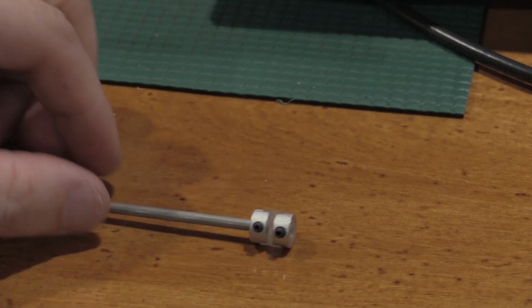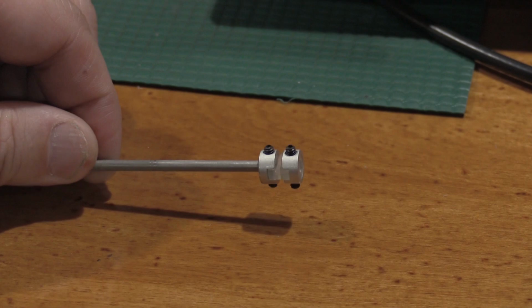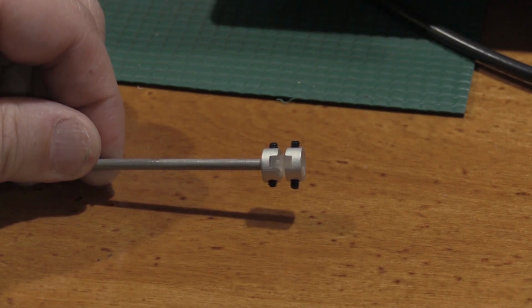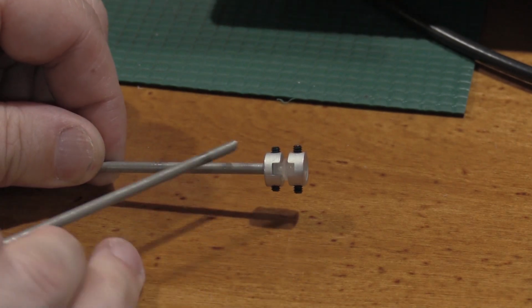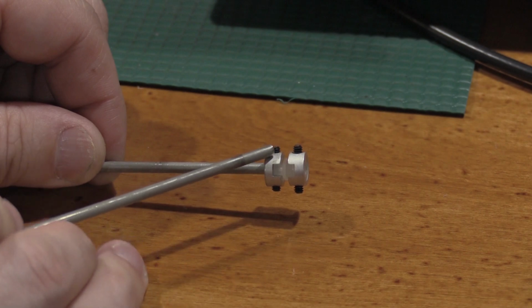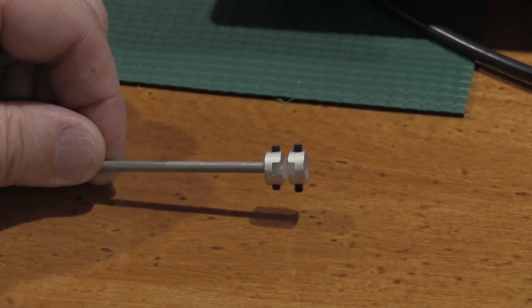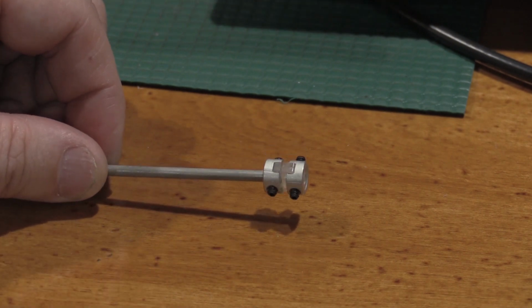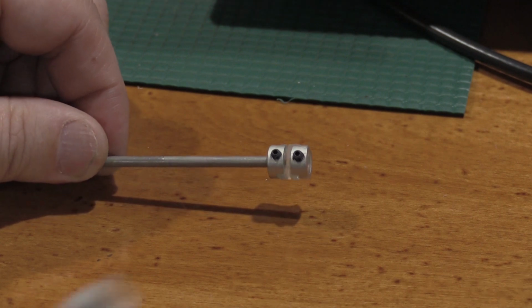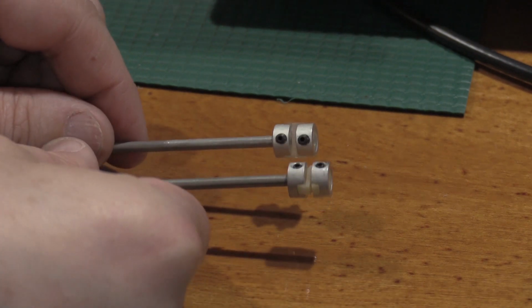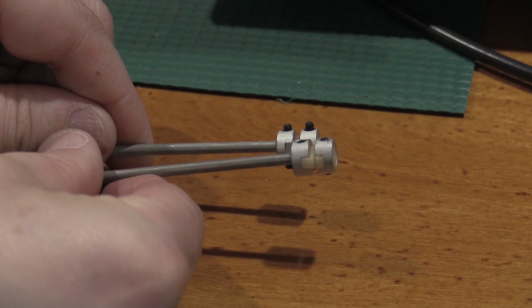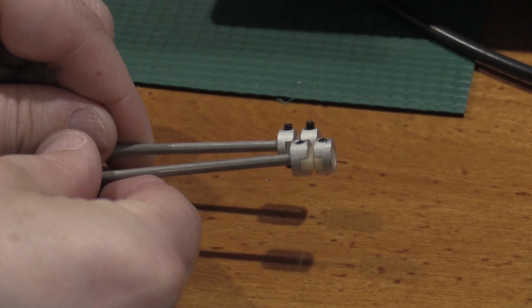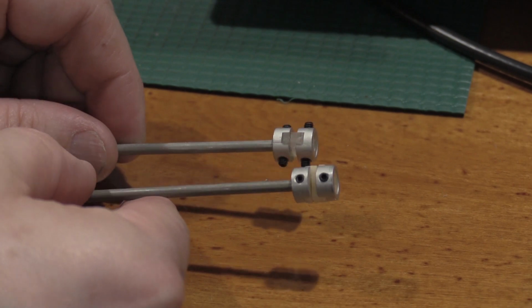Well, it seems we are not the first ones here. Comparing it with channel 2, this is the coupler that's in there. It's the right coupler, but it's the wrong screws. These are way too long to be used in this application, and they're grinding on that cable. This is the correct coupler that should be there. So we are not the first ones here, but we will get it back to normal.